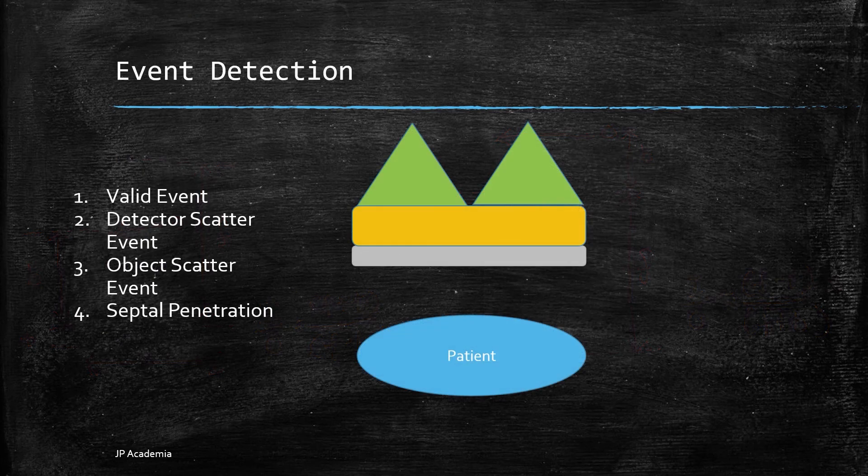There are four types of event detection that may be detected by the gamma camera, illustrated here. First, we have the valid event. In this event, a gamma ray is emitted parallel to the collimator holes and it passes through the hole until it reaches the sodium iodide crystals, depositing all of its energy at a single location only.